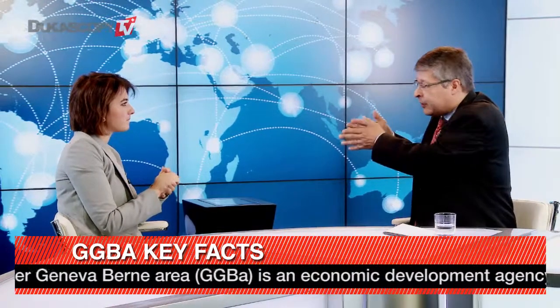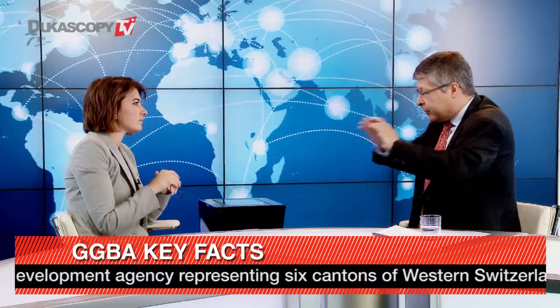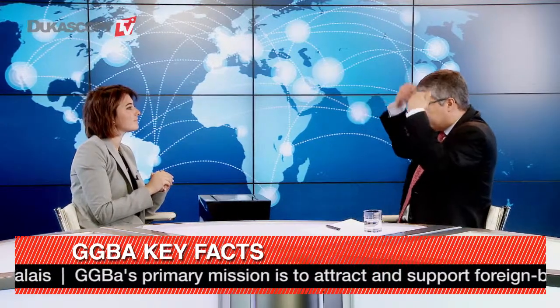Is there the argument here with so many regulations and with it being quite a complex idea almost, does CE marking perhaps kill or dampen potential for innovation? Actually, it does not, for the following reason. The CE marking system has two parts. One part is what is called the CE directive, and the CE directive is mandatory. The CE directive is a very general document written in a very legalistic language, and this is compulsory. In addition, for each product, you have what is called the harmonized standard. The harmonized standard is a very thick document written in very technical terms, and this is not compulsory. However, if you meet the harmonized standard, there is a presumption that the CE directive is fulfilled.